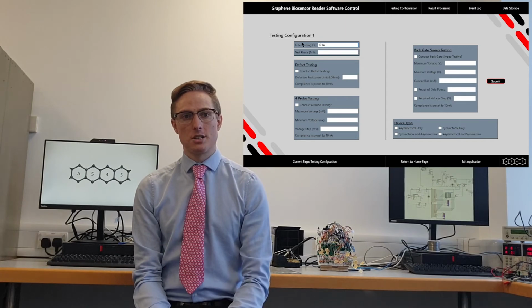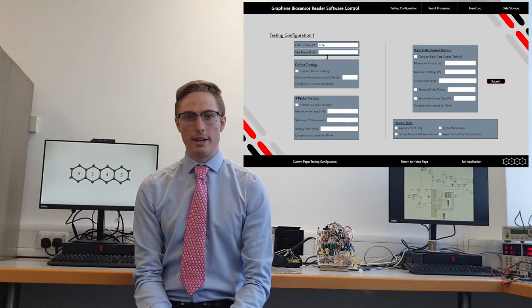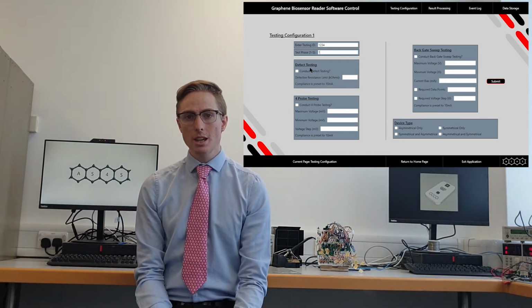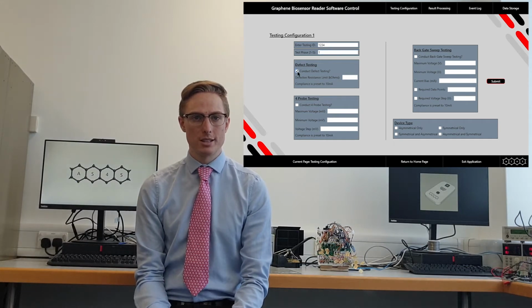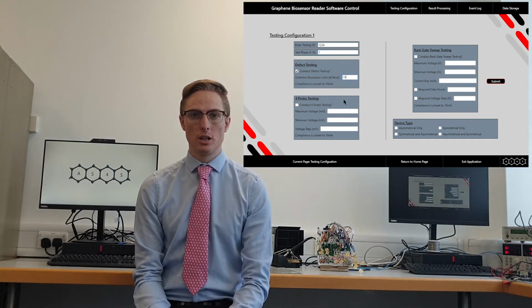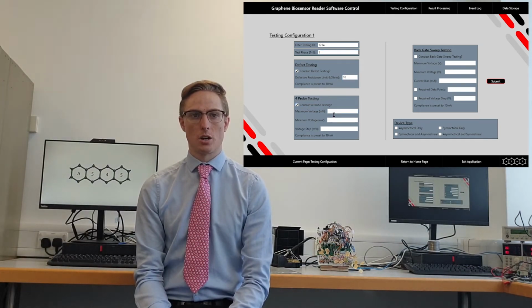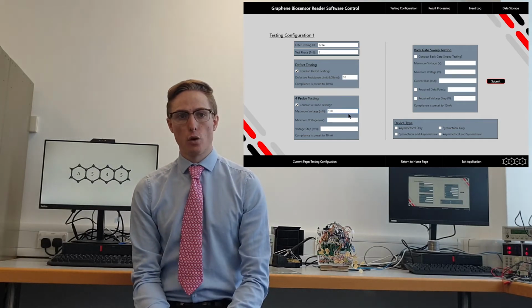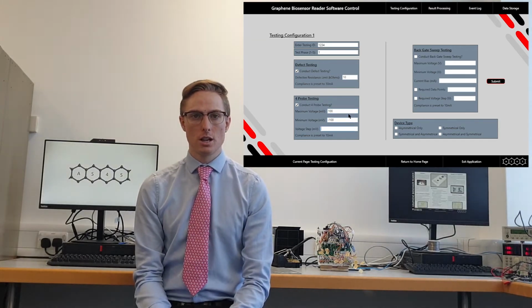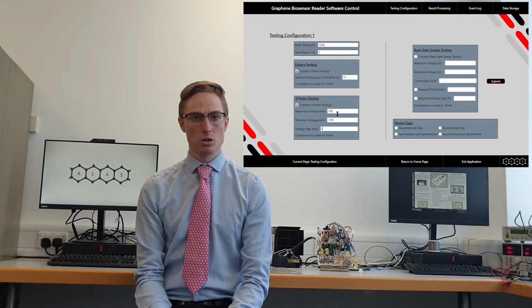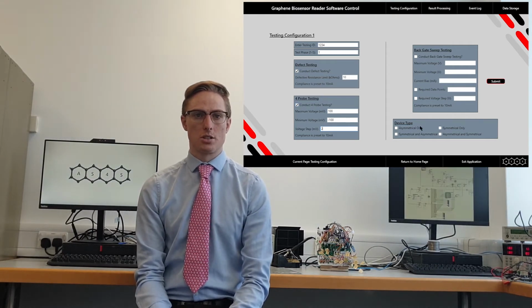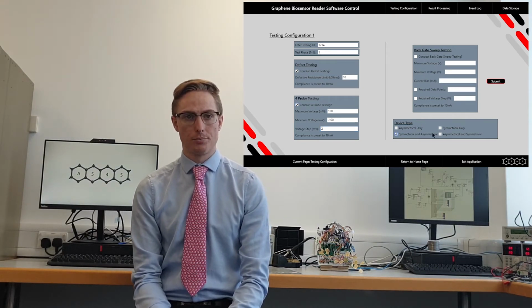If the defect test is to be conducted, the resistive limit can be set by the user. Any sensor with channel resistance greater than this value will not be included in further, more accurate tests. If the 4-probe test is also to be conducted, it can be configured by defining the voltage range and voltage steps desired to be captured.